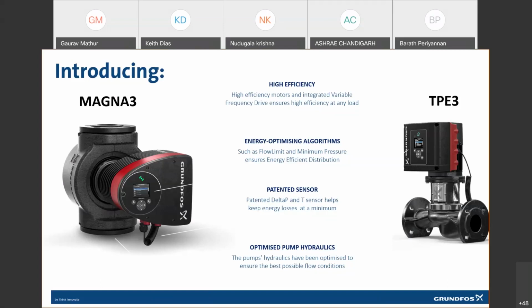So when I go for a distributed pumping system, we have to make sure that the pumps are designed for the highest possible efficiency, to ensure that we are able to achieve operational savings which can make the system commercially viable. That was the first thing we achieved. The second is that the entire intelligence is there in the pumps. As you can see on your screen, the Magna 3 and the TPE3 pumps of Grundfos have built-in intelligence and controllers. They have built-in sensors which ensure that the performance localized to that particular equipment is optimized at any point of time.